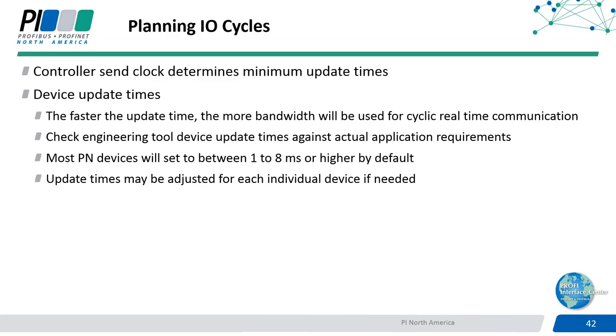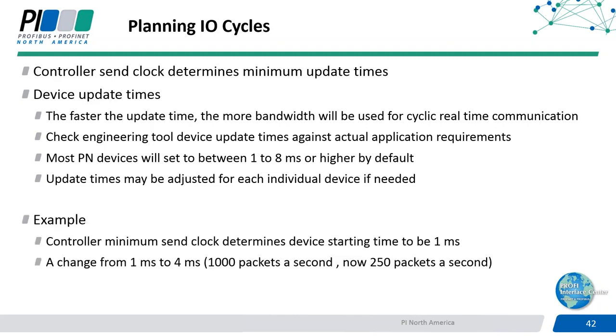So for example, what happens if you pull in 64 devices in your configuration, and now the tool automatically sets all of those 64 devices to update at 1 millisecond? So the question is, do you need that for your application? You really need to check and adjust the update time if necessary on the devices based on your actual application requirements in the topology. For example, let's say we've got a device that we set up at 1 millisecond. That means that device is going to be sending 1,000 packets a second. Now, granted, the PROFINET telegrams are going to be a lot smaller than a TCP/IP message. But if you get a lot of these small messages, again, that can increase your network load.